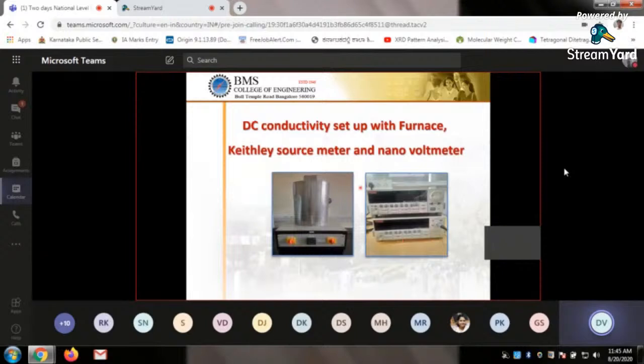Coming to the next, we are studying DC conductivity. This is a simple setup again, with a furnace. The photo quality is not good. We have a Keithley source meter and a nanovolt meter. We are passing current and measuring voltage. So with current and voltage, we can calculate conductivity. Again, we have one more setup.